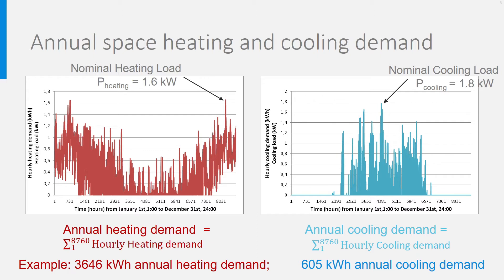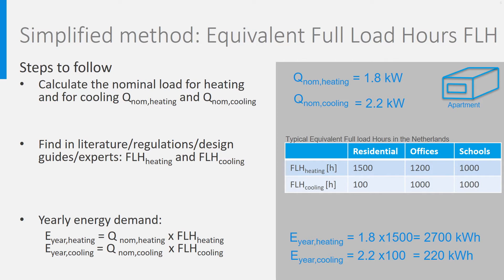However, you may not always have the needed meteorological data to make such calculations. That's why simplified methods can be used. One of these is the use of equivalent full load hours. These equivalent full load hours are determined by statistical analysis of the ratio of yearly energy demand and nominal power for a large number of existing buildings. Once you know these full load hours for your region and type of building, you just multiply the nominal power by the full load hours to get an estimate of yearly energy demand. Generally, you can find the full load hours in national guidelines.